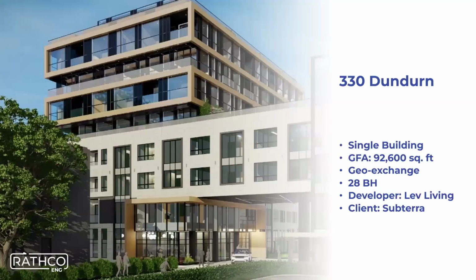We can take this down to a much smaller building. I don't like rules of thumb, but the rule of thumb for GeoExchange systems is anything north of 100,000 square feet for these types of deep boreholes - they're not really that deep, I'll explain that - at like the 850 foot range, 100,000 square feet plus, nine times out of ten it's going to be a slam dunk, GeoExchange is going to make a lot of sense. At that 50 to 100,000 square foot level, we're in the 'it depends' category based on variables - maybe the geology needs to be very favorable, maybe the type of building loads need to be favorable. Anything less than 50,000 square feet in the real estate sector is a bit of a struggle to make the business case work.